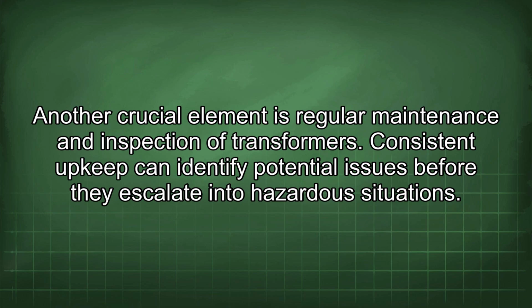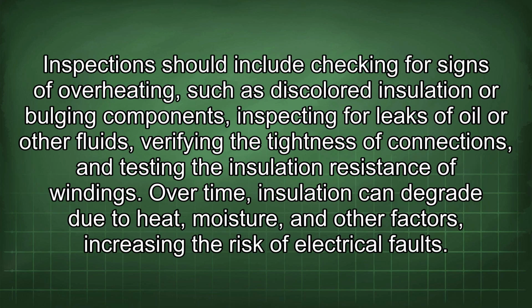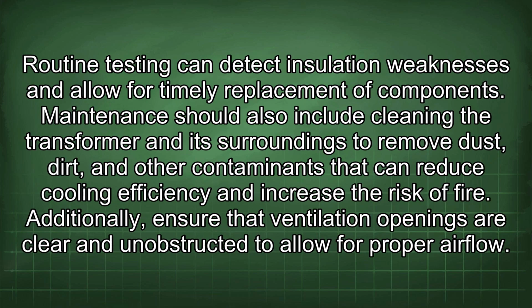Another crucial element is regular maintenance and inspection of transformers. Consistent upkeep can identify potential issues before they escalate into hazardous situations. Inspections should include checking for signs of overheating, such as discolored insulation or bulging components, inspecting for leaks of oil or other fluids, verifying the tightness of connections, and testing the insulation resistance of windings. Over time, insulation can degrade due to heat, moisture, and other factors, increasing the risk of electrical faults. Routine testing can detect insulation weaknesses and allow for timely replacement of components.